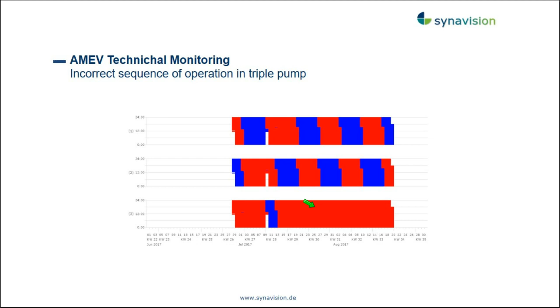In this sequence the third pump should always also be a part, but in many buildings we find that it isn't. Usually the third pump was set in operation during the commissioning phase manually, and in the end somebody forgot to integrate it into the sequence of operations, so it's continuously running, using a lot of electrical energy and potentially messing up the hydronic system as well.